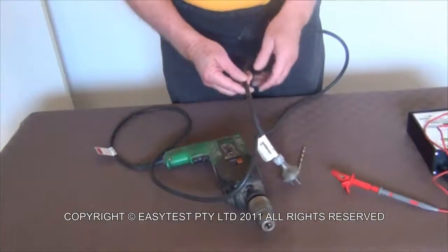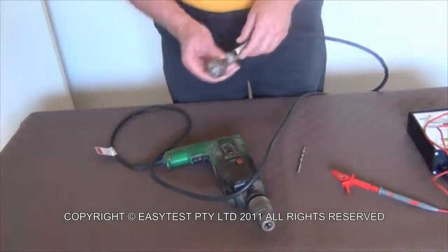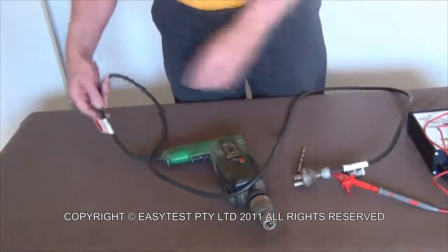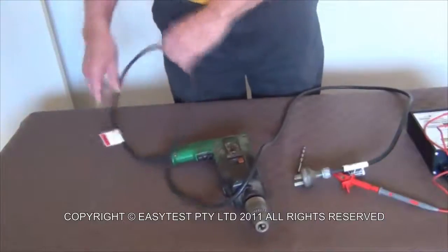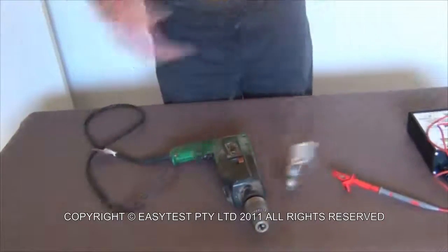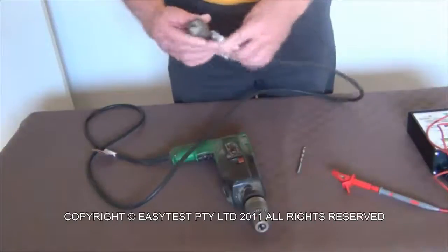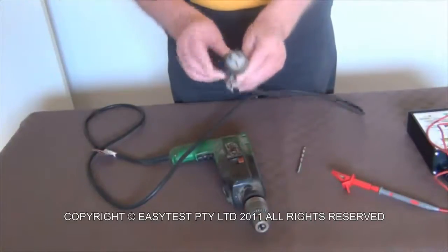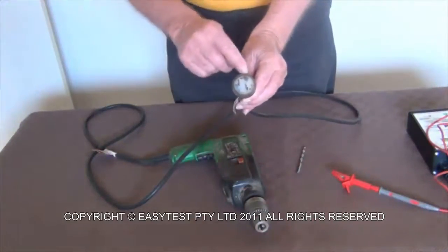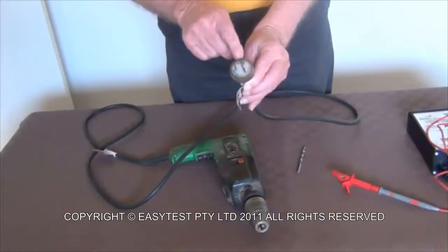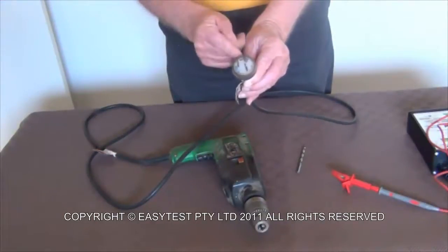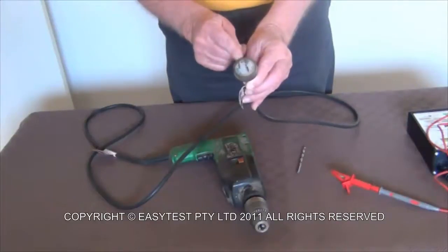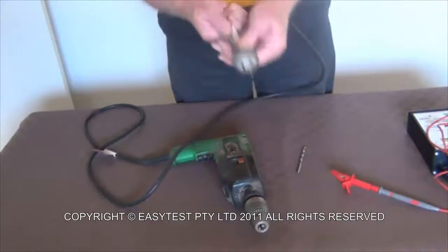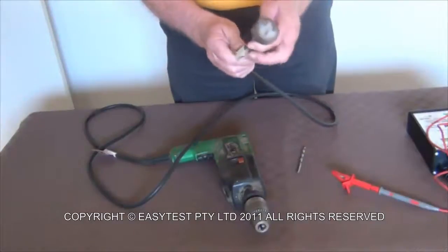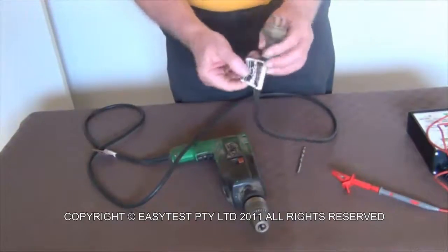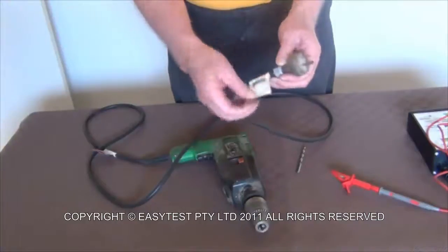Here's a Class 2 drill that I took from a workshop the other day. Did my normal physical inspection, checked the lead. Noticed that the plug isn't the original plug, it's been rewired. So by looking in the back, I checked the polarity and I checked that the wire is actually looped around the labyrinth so that it gives stress relief if somebody pulls the cord. And it has an existing danger tag.